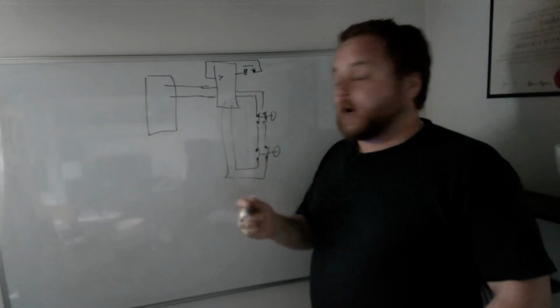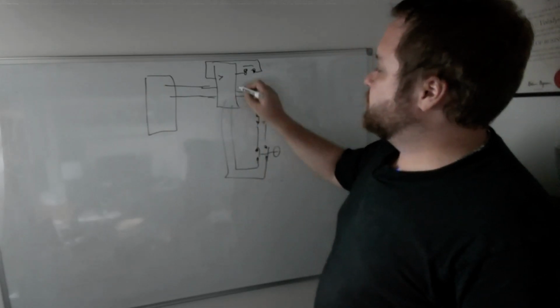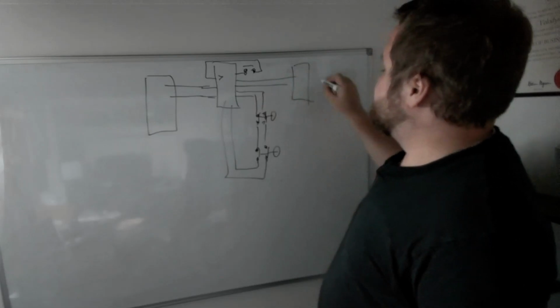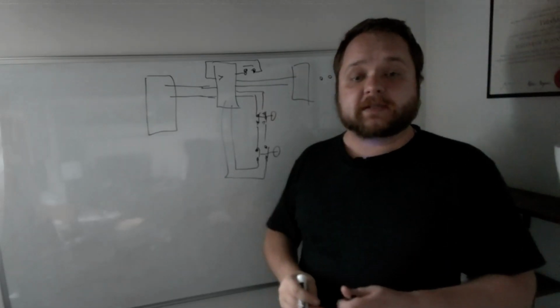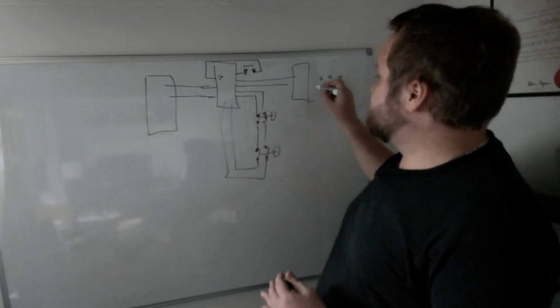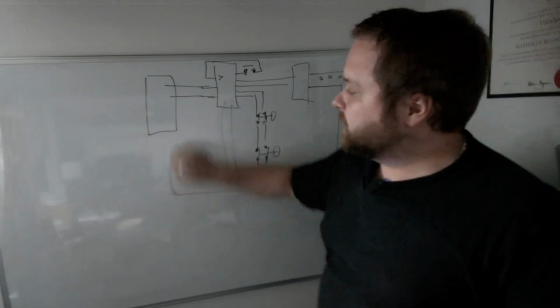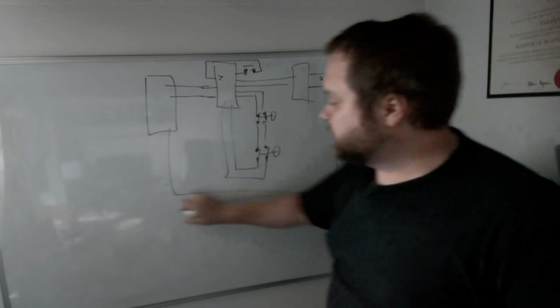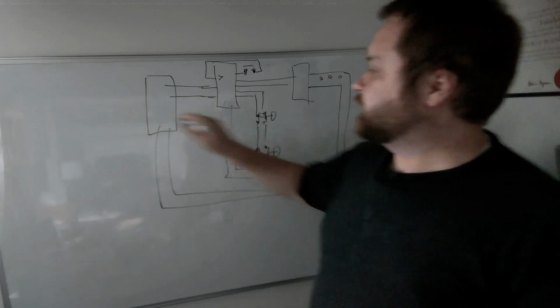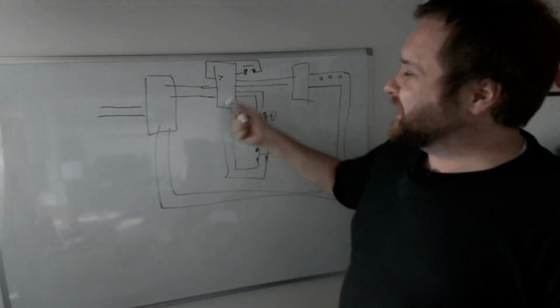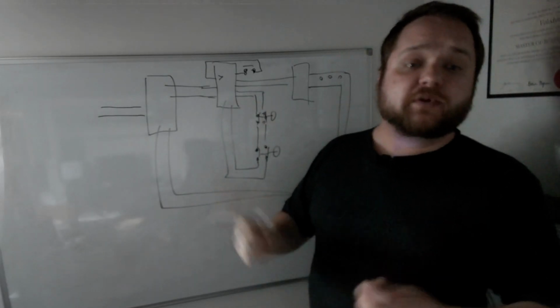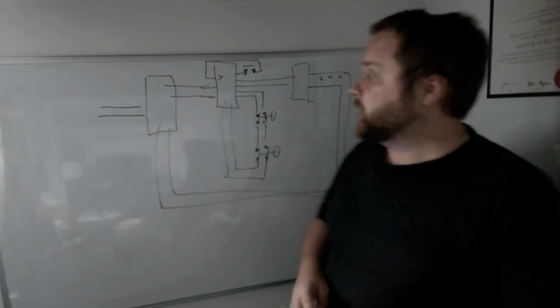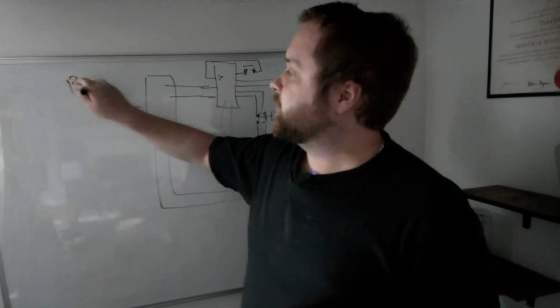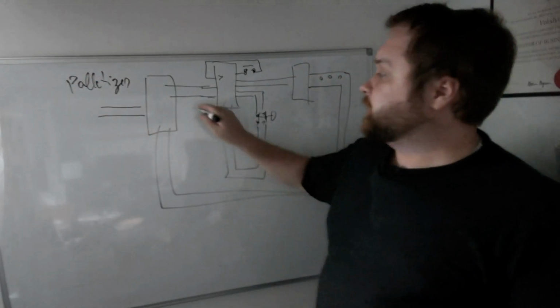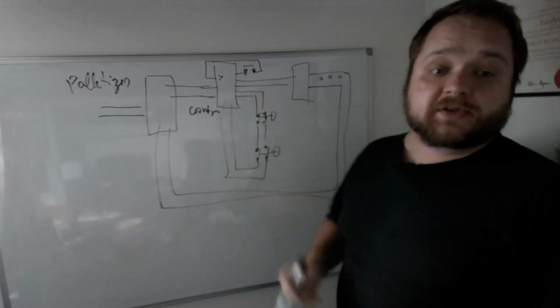And the reason why you need to do this, right, and so this is going to be the chain which will basically check an array of safety relays, is that you can create circuits that are going to be checking for different areas where this is basically daisy chained until it comes back to what's called a master safety relay, which then allows very specific sets of equipment to run. So to give you an example, this can be done in a palletizing area where you have the master circuit responsible for the palletizer, the secondary circuit responsible for some of the conveyors, and the tertiary circuit responsible, for example, for the stretch wrapper.